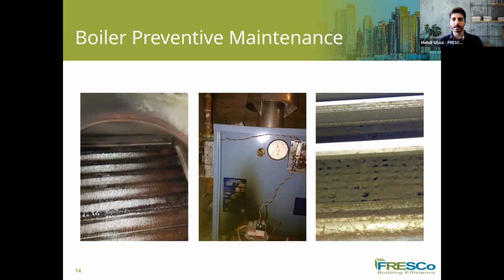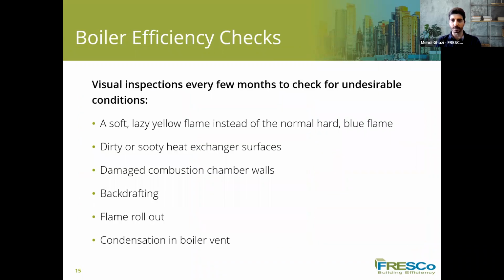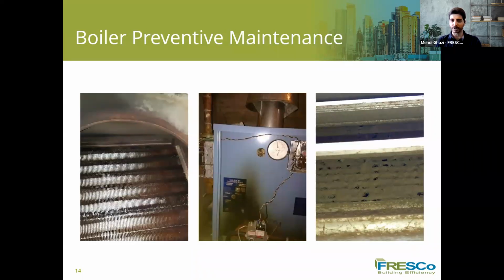The solution is easily finding contractors that do this type of maintenance as a part of their service, so they can easily rinse the heat exchanger with hot water and dissolve the white powder, and also brush the heat exchanger. This can significantly increase the efficiency of the boiler, and we can have a better temperature in the building, and also more satisfied tenants.